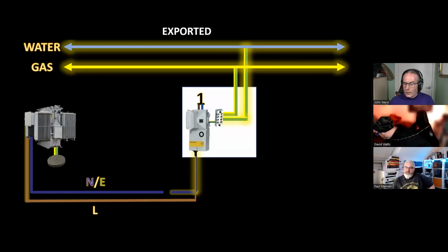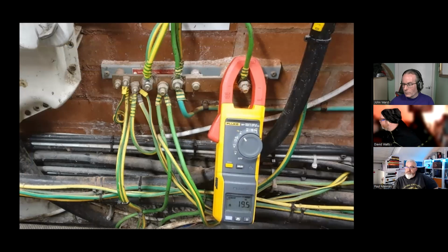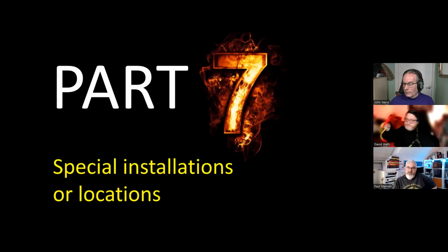One of the interesting things is somebody rang me the other day and said they had what they thought was a broken, diverted neutral. One of the easy quick wins to figure out what it's from is, rather than disconnecting the earthing conductor, if you've got a 4-way block, just disconnect all the bonds, reattach them, have your clamp on your earthing conductor and see where your current's coming from. Then you'll know whether it's coming from or going through your gas or your water, because obviously they'll have different impedances. So just be wary, folks, that diverted neutral current is a thing. It does exist. Nearly 20 amps of it on that picture there.